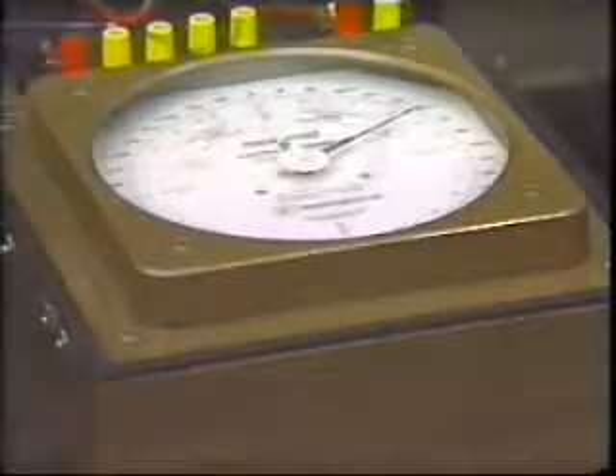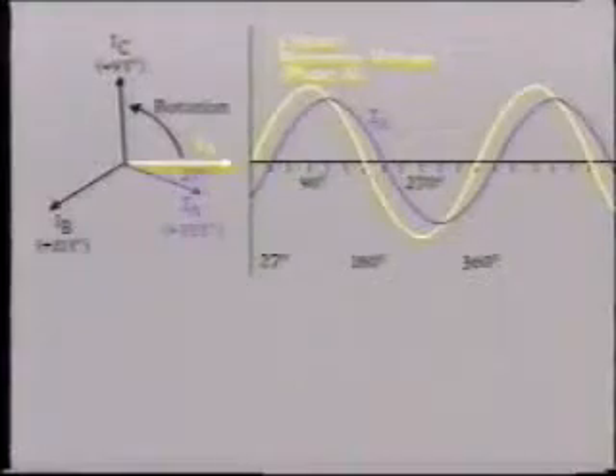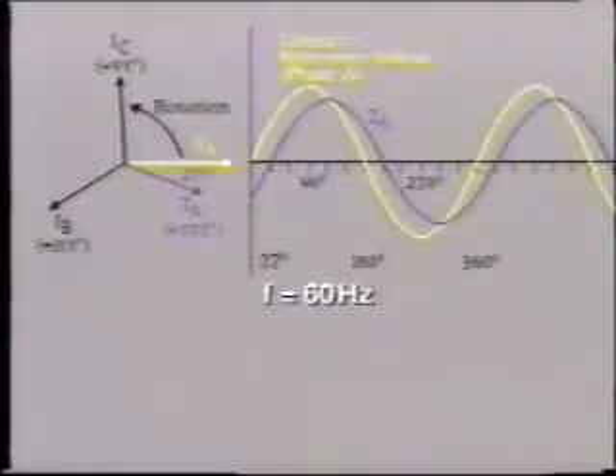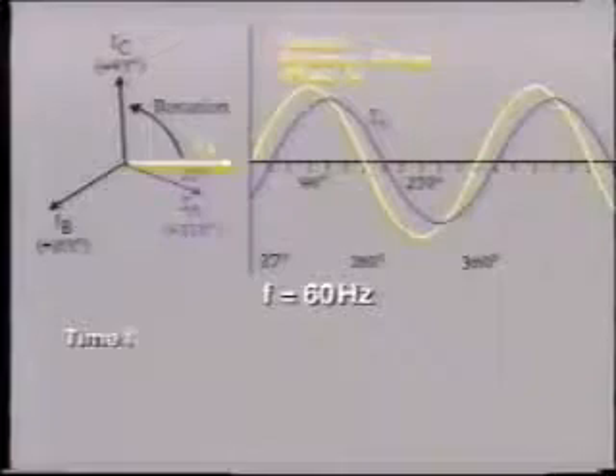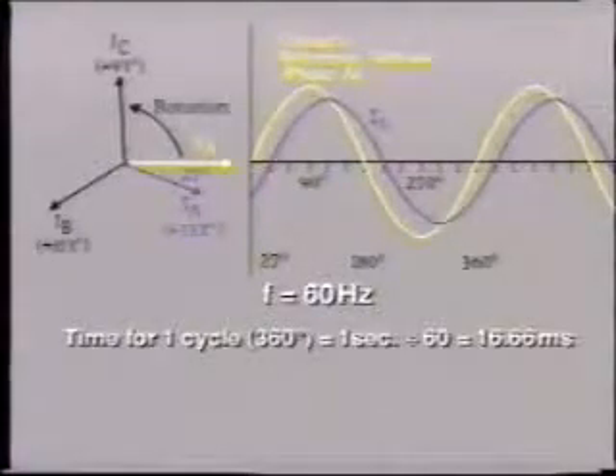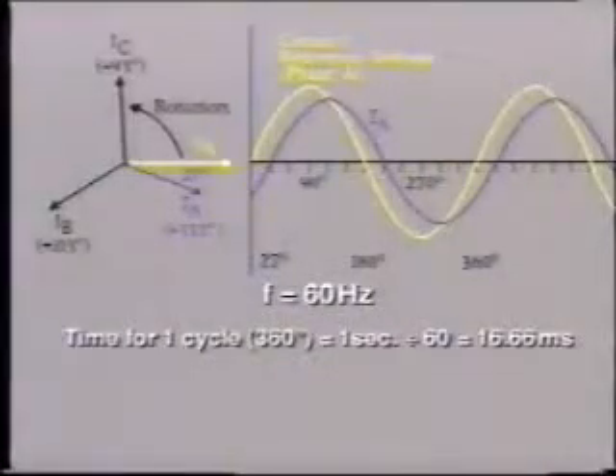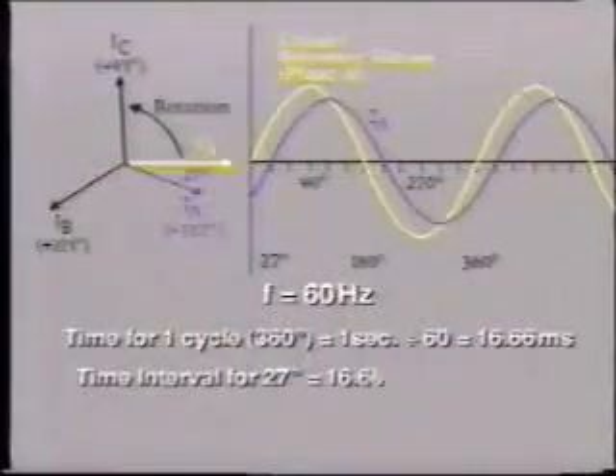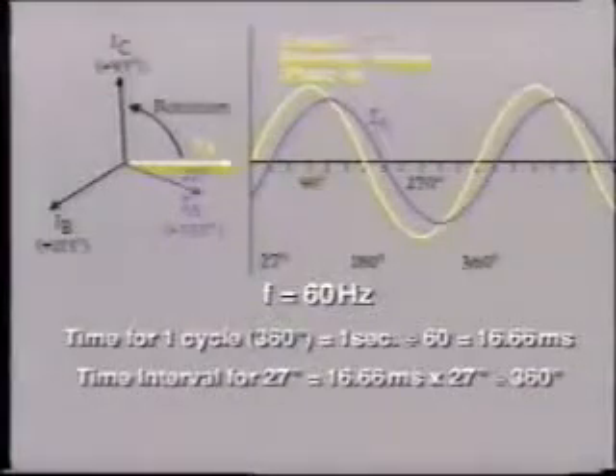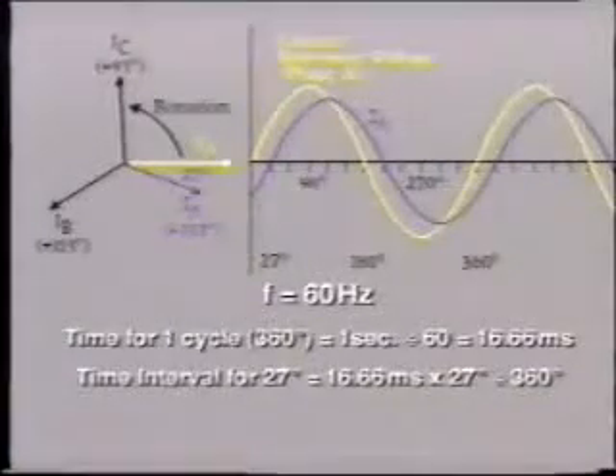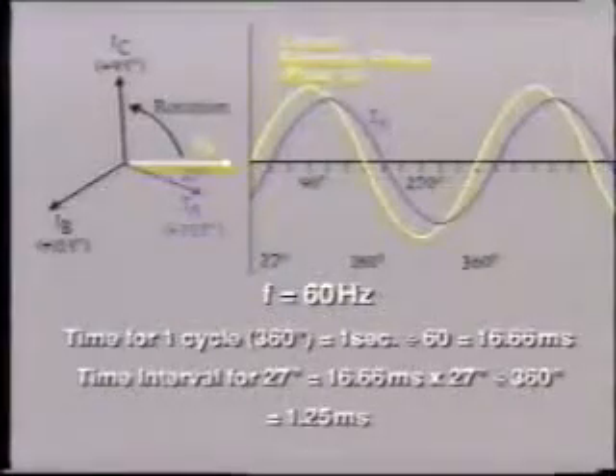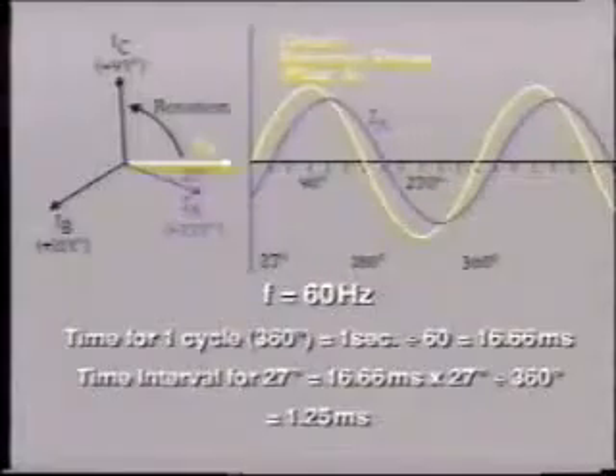In order to calculate the phase angle, the instrument must very precisely measure frequency of the signals and time. Suppose in this test that the frequency was precisely 60 hertz. What would be the measured time interval between VA and IA? The time for one cycle, that is 360 degrees, will be 1 second divided by 60 equals 16.66 milliseconds. The time interval for a phase difference of 27 degrees is therefore equal to 16.66 times 27 divided by 360 equals 1.25 milliseconds. So you can see how accurate the timing measurement must be.